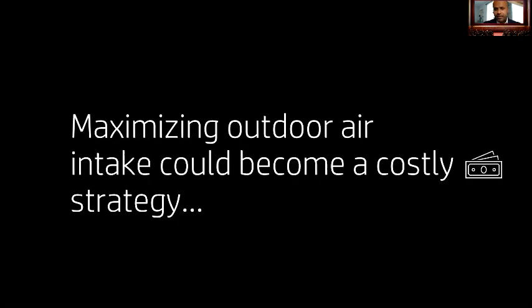Now, except for healthcare facilities, most HVAC systems condition a mix of outside air with recirculated air from the same space. The recirculation of air is a measure for saving energy, but as we know now from recent evidence that ventilation systems could transport airborne contaminants, including infectious viruses, from one space to another, avoid air recirculation. While it is easy for us to say 100% outside air, depending on your weather conditions, maximizing outdoor air intake could become a costly strategy.